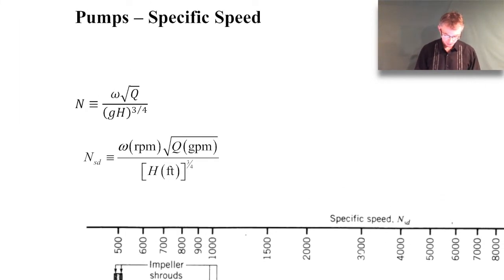And so the key parameter for calculating specific speed is right here. N is our specific speed, and it's defined as the rotational speed of the pump, omega, times the square root of the flow rate through the pump, Q, divided by g, which is the acceleration due to gravity, and H, which is the head rise across the pump, all raised to the three quarters power.